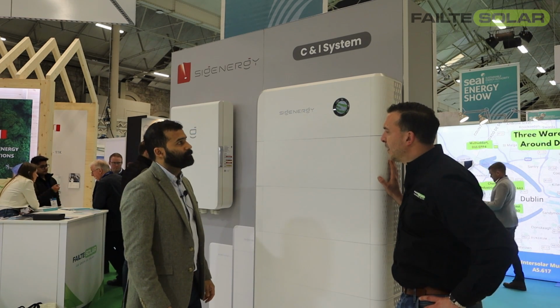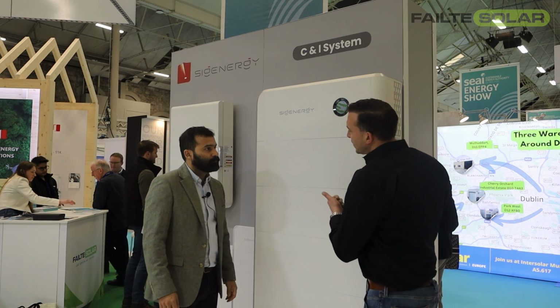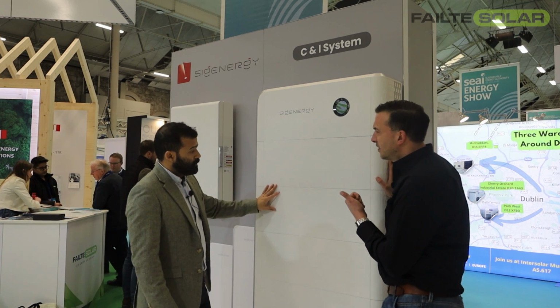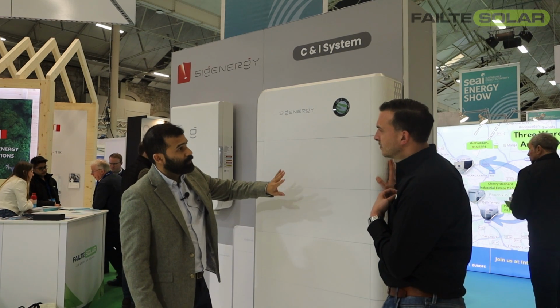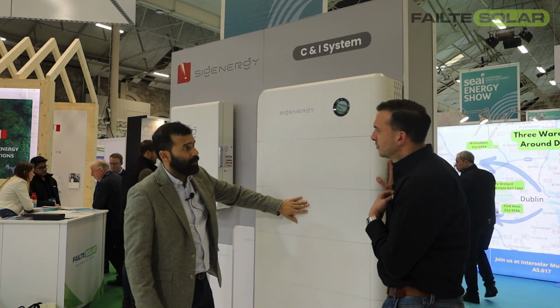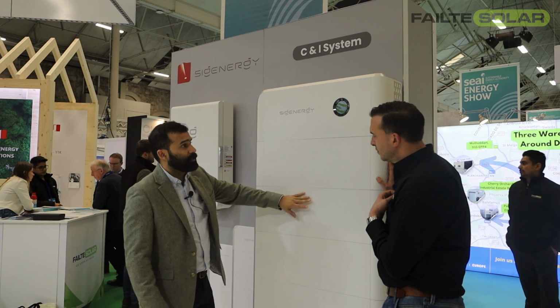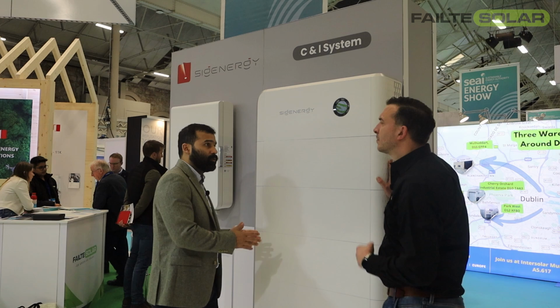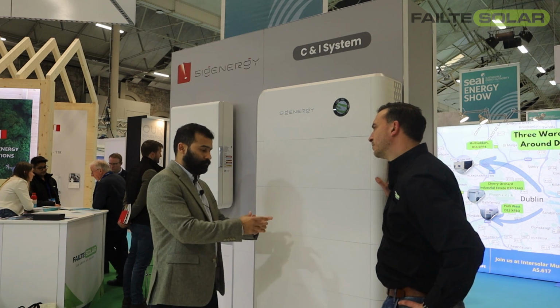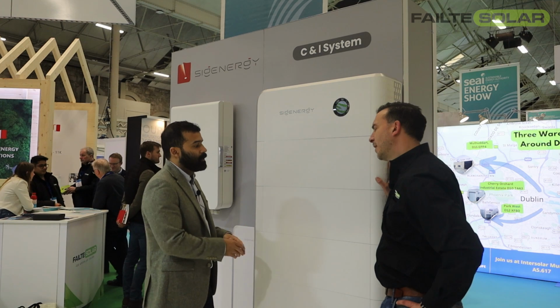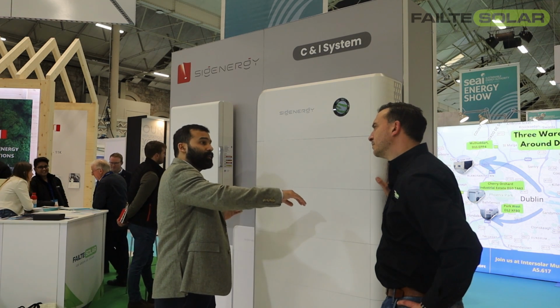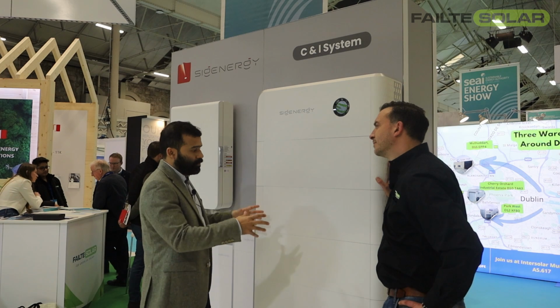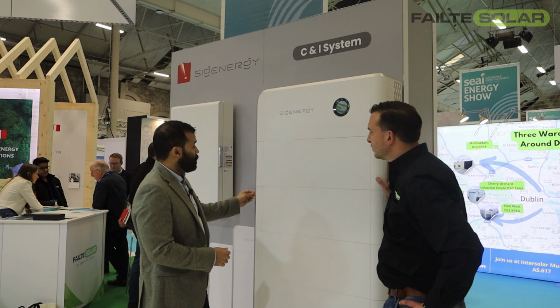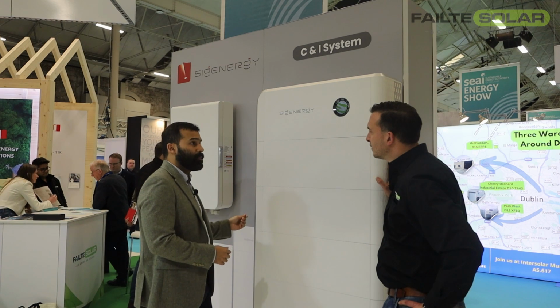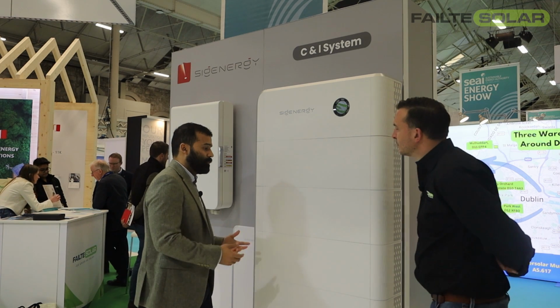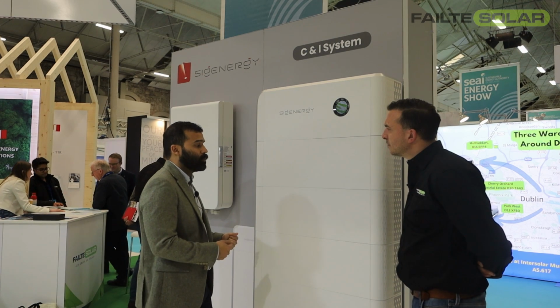Just to remind you - built-in fire extinguisher dedicated for every battery pack. We have aerogel insulated pads around every battery cell to avoid spreading of temperature from one cell to another. We have high resistant insulating pads around the whole battery pack, again to contain the temperature. In the event of high pressure after a fire extinguisher event, there's a decompression valve that will trigger automatically to release the pressure inside the battery pack and make it safe to change.